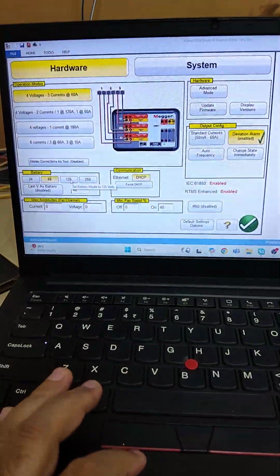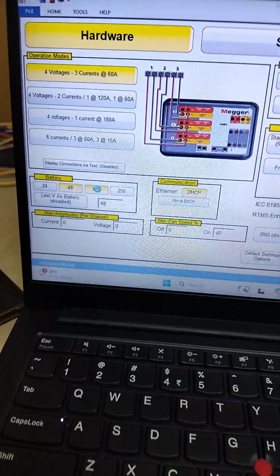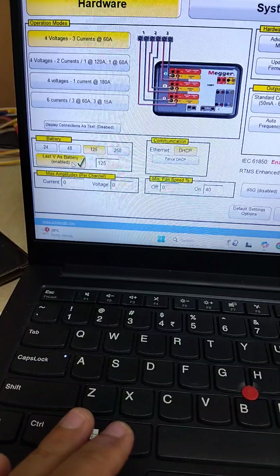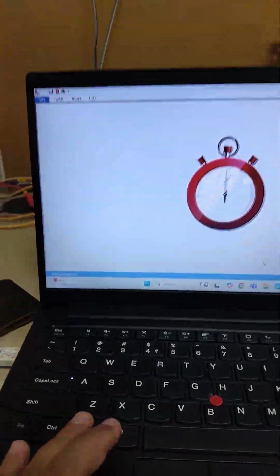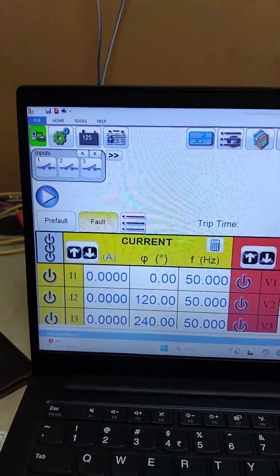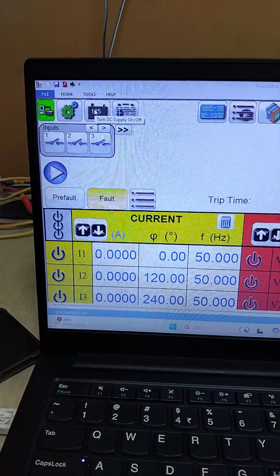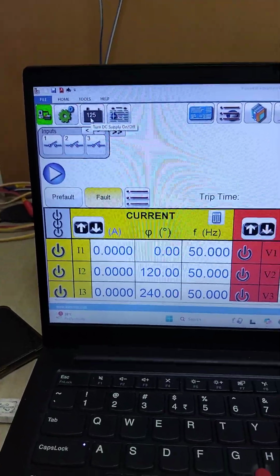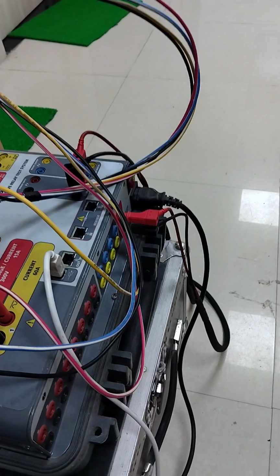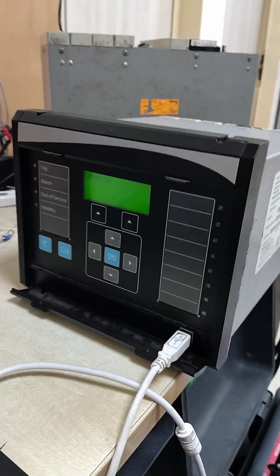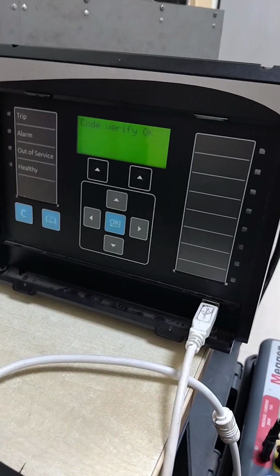So first check in the device. This device is 110 to 250 volt AC, so we can select any voltage range between that. So I'll go with 125 and enable it. Once you enable, you can see a voltage icon here with the same voltage that you entered. So just press it, so it will supply the power to the device and the device will boot.